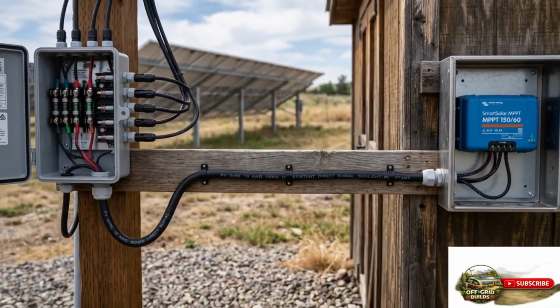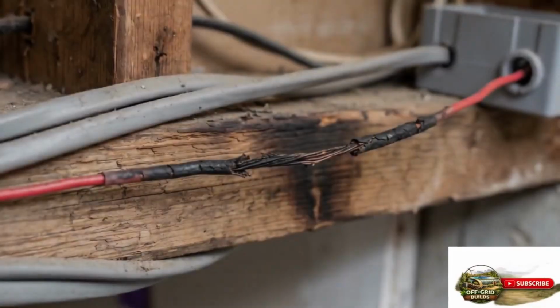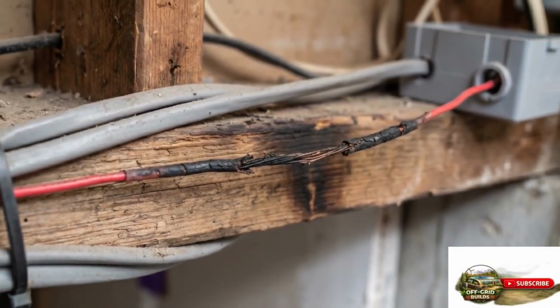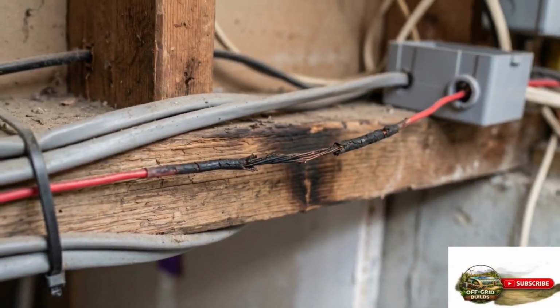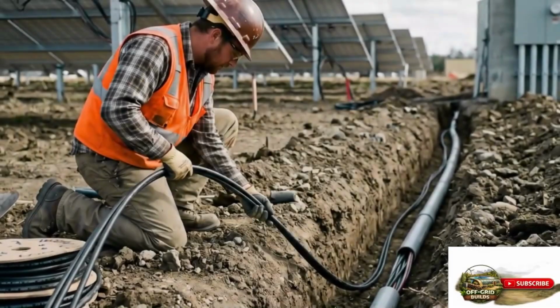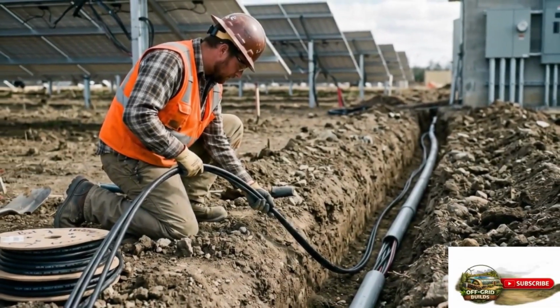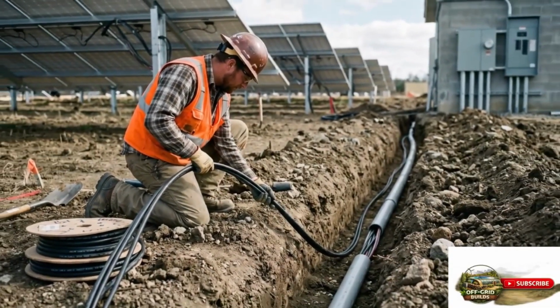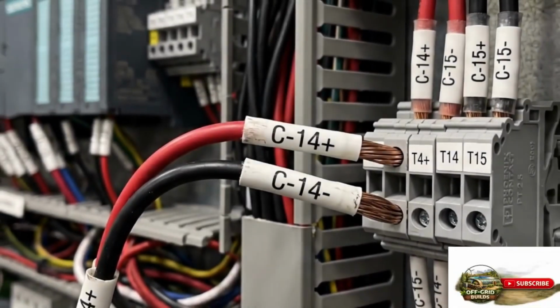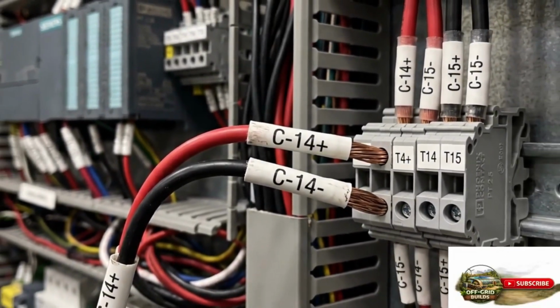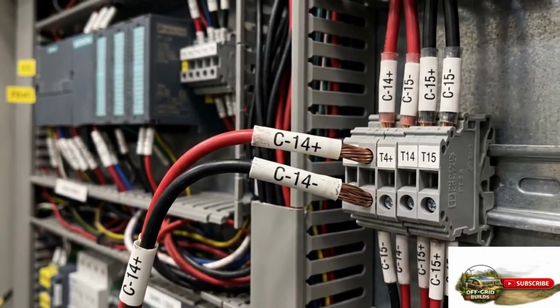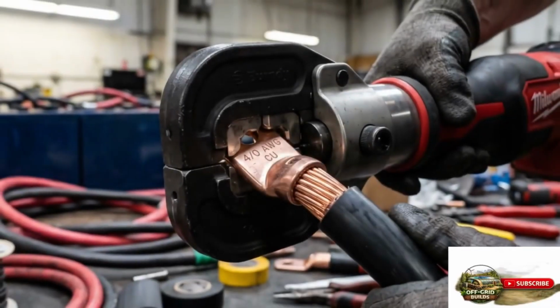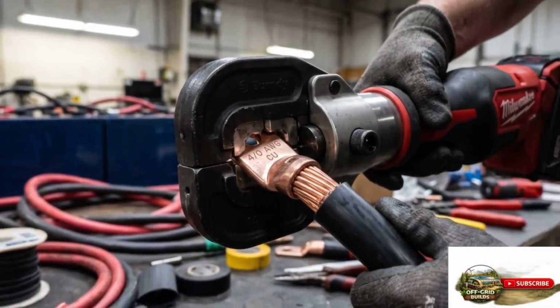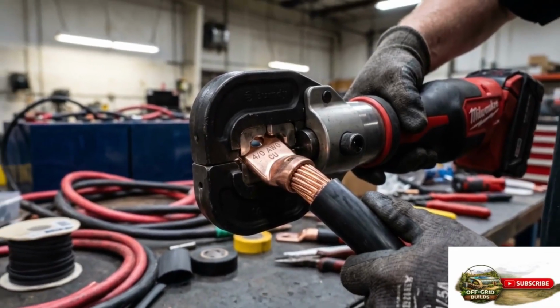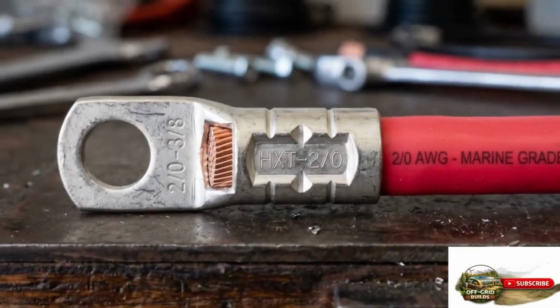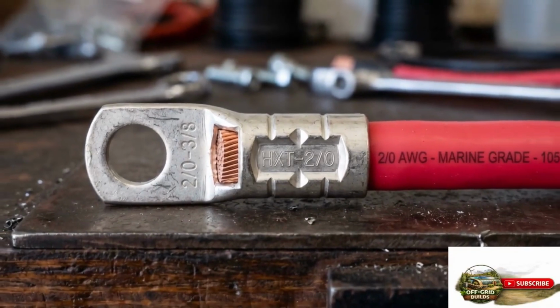The fundamental principle of wire sizing is that wire must be sized to carry the maximum expected current without excessive voltage drop or overheating. The National Electrical Code provides guidance on wire ampacity by gauge and installation method, and local jurisdictions in most American states require NEC compliance for permitted electrical installations. For unpermitted rural installations, the NEC still represents the correct safety standard even where it is not legally mandated.